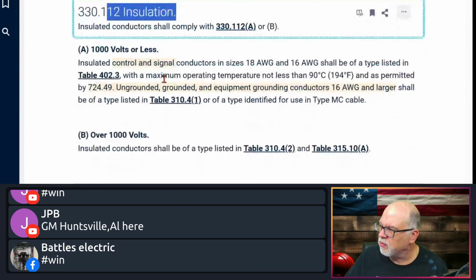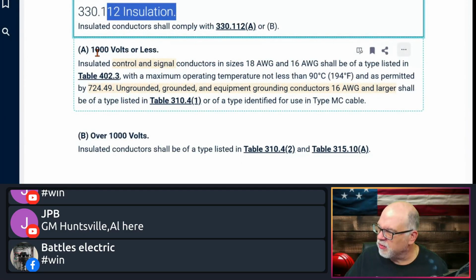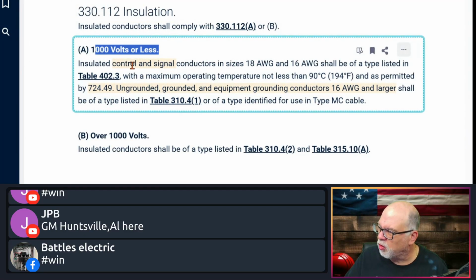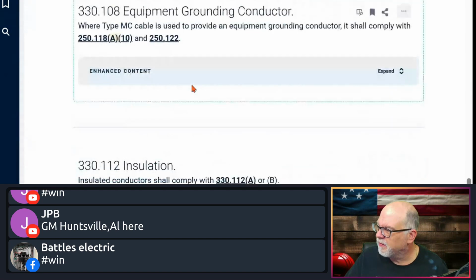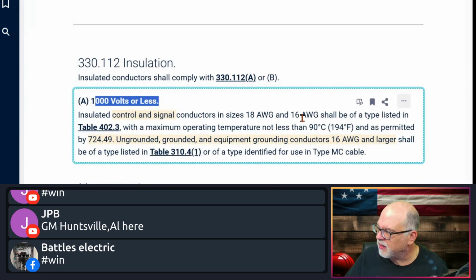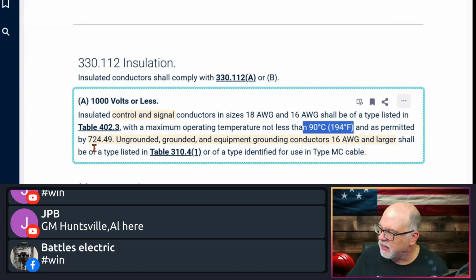Here's your insulation. Where insulated, it says 1,000 volts or less. It says insulated control and signal conductors of 18 and 16 shall be the type listed in table 402.3. So you've got different types of insulated materials with a maximum operating temperature of not less than 90 degrees C, and as permitted in 724.49, ungrounded, grounded, and equipment grounded conductors of 16 and larger shall be the type listed in 310.41 or the type identified for use with type MC cable.